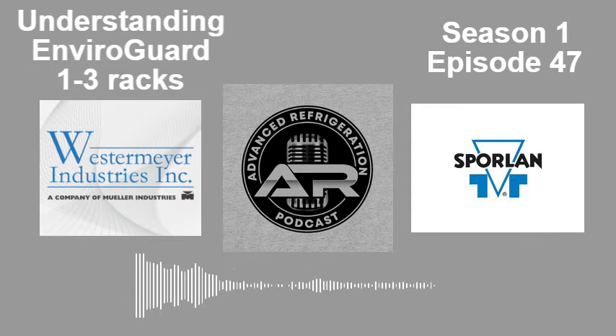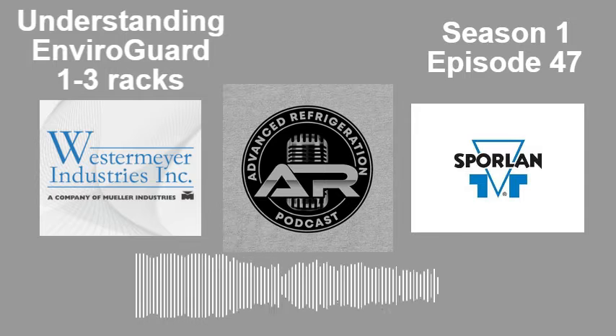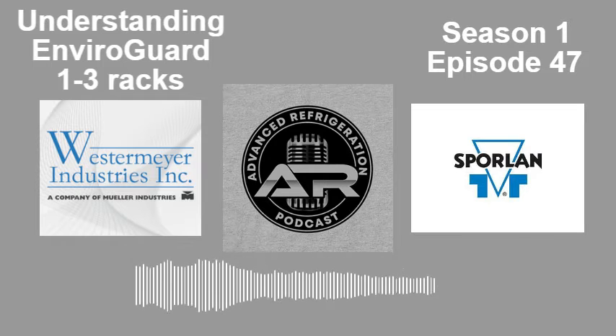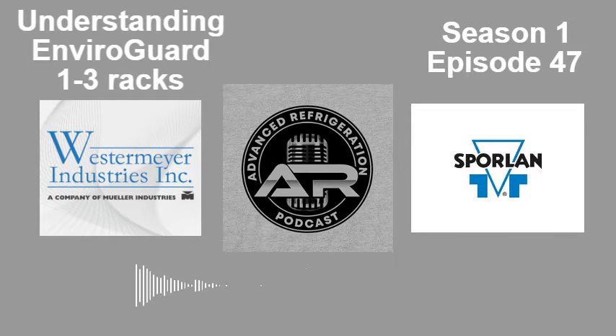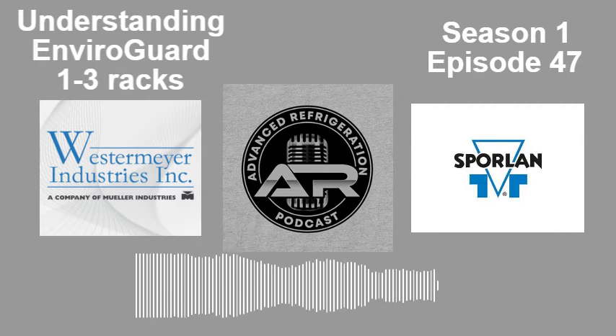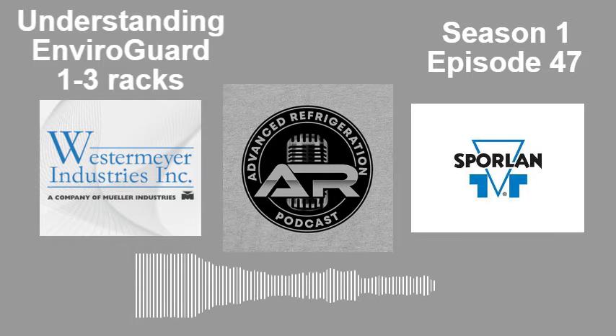What we do by eliminating the receiver is we reduce the charge. The biggest advantage to Enviro-Guard is the charge reduction. Instead of an extra 300 to 400 pounds for a receiver, now we have a critically charged rack where you lose 50, 60 pounds of gas. You now have a case running warm and you're out there when you've lost 50 pounds of gas, instead of losing 300 pounds of gas before you get an alarm and you're out there looking for it.